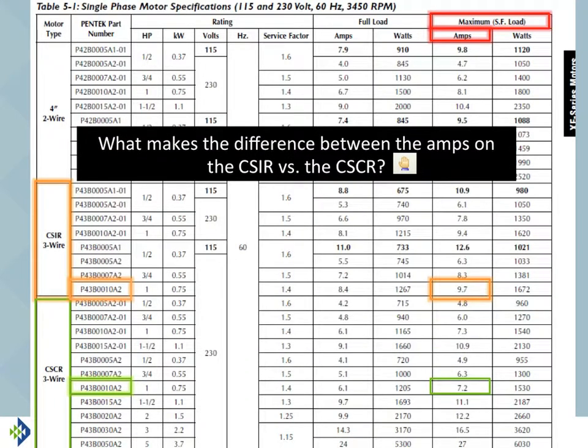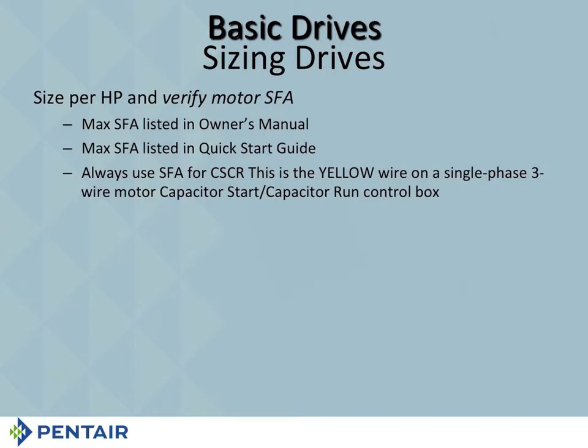What makes the difference between the amps? It's going to be that running capacitor. The running capacitor makes the difference here. And because there is a running capacitor, it is going to be hooked up to the starting coil. And because it's hooked up to the starting coil, it means that you're sharing or spreading those amps out. You're not putting all that amps on one wire. And so that's why that's important. All right? That's your Cap Start Cap Run.